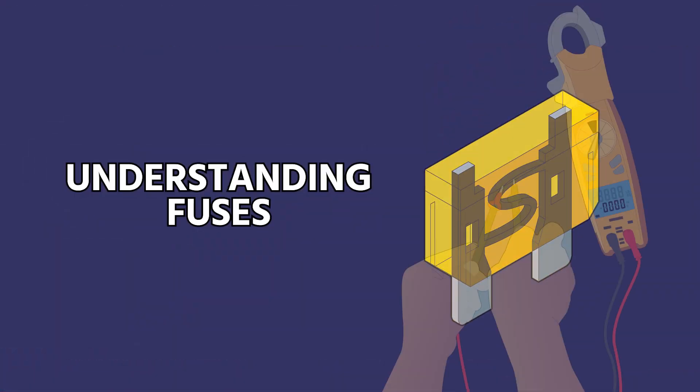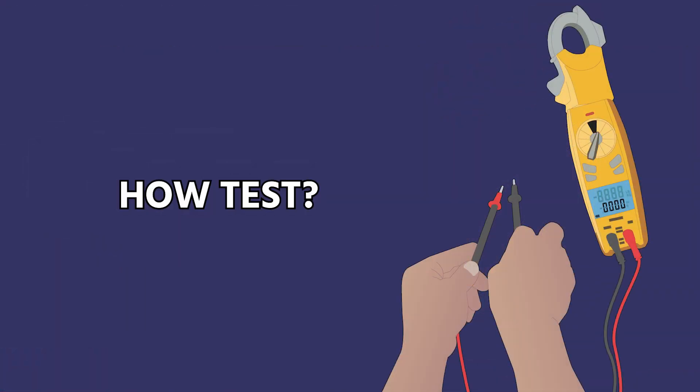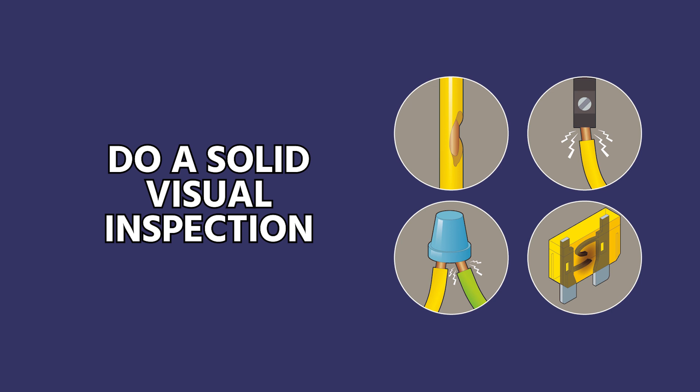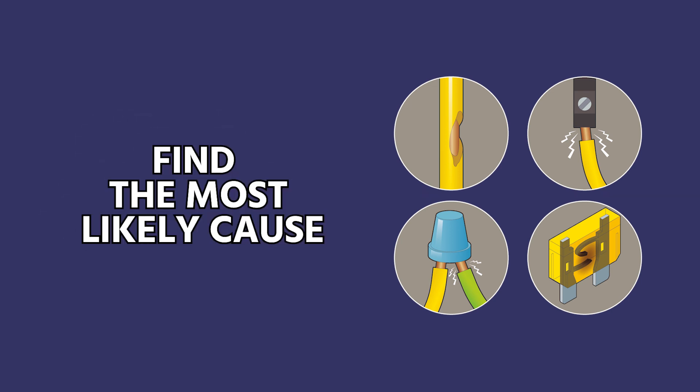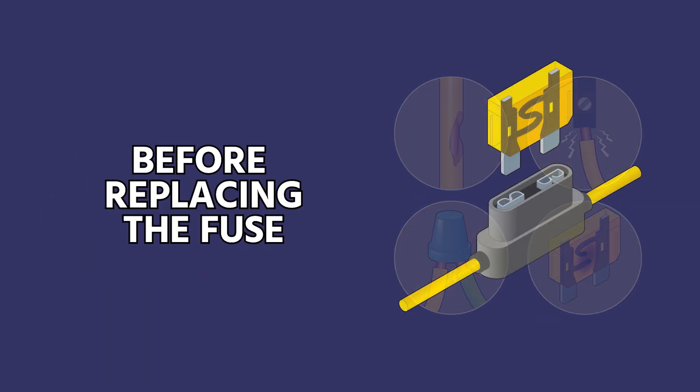But it all starts with understanding fuses, understanding how to use your meter, how to test them, and then how to do a solid visual inspection to find the most likely cause of the low voltage short before you just start replacing fuses over and over again.